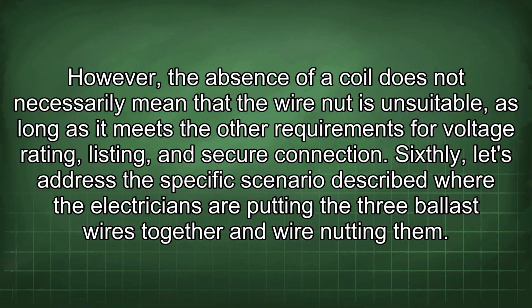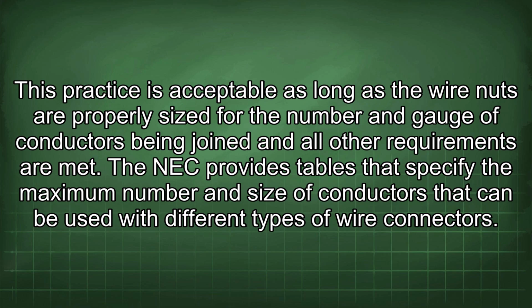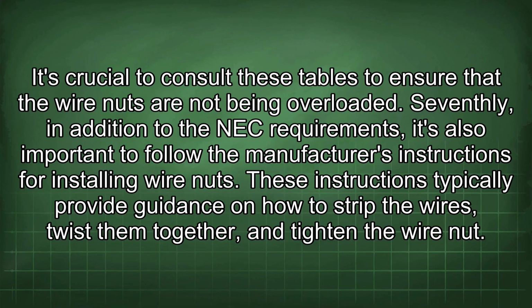Sixthly, let's address the specific scenario described where the electricians are putting the three ballast wires together and wire nutting them. This practice is acceptable as long as the wire nuts are properly sized for the number and gauge of conductors being joined and all other requirements are met. The NEC provides tables that specify the maximum number and size of conductors that can be used with different types of wire connectors. It's crucial to consult these tables to ensure that the wire nuts are not being overloaded.